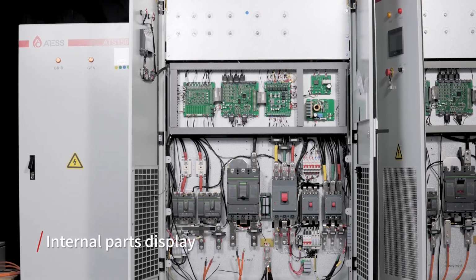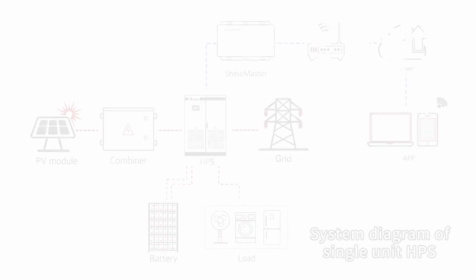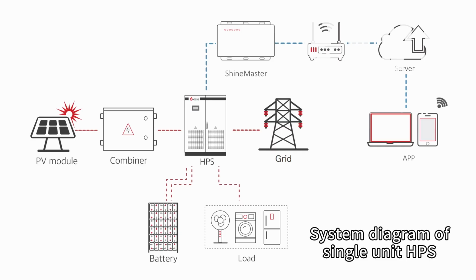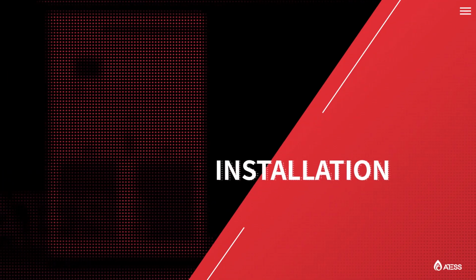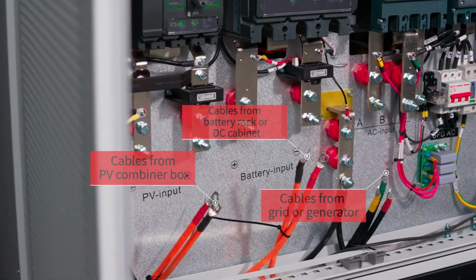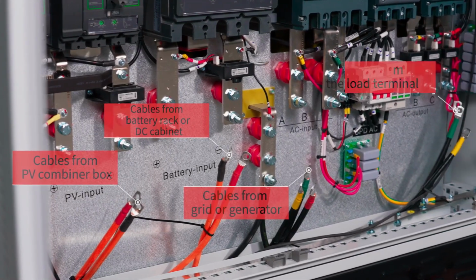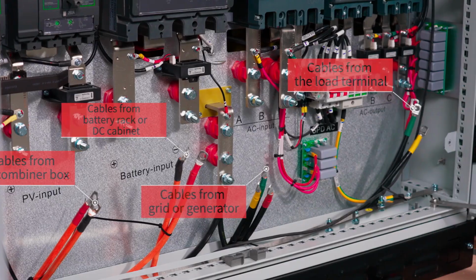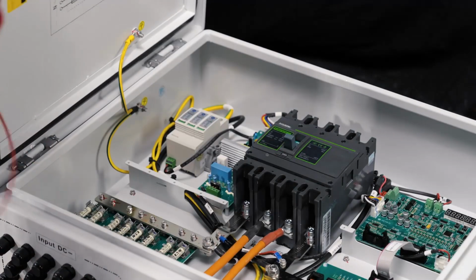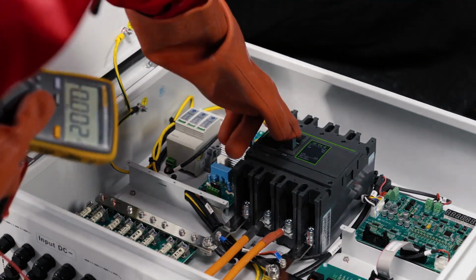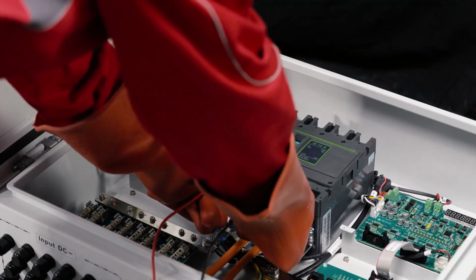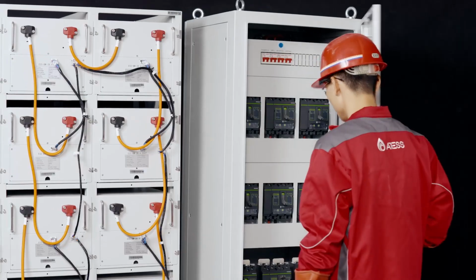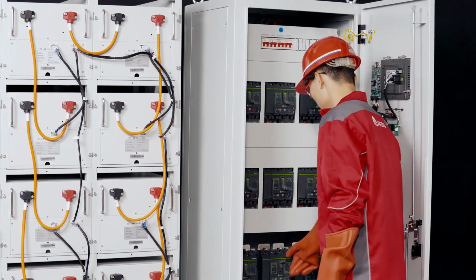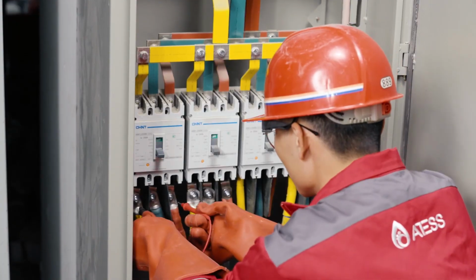Before we start wiring, firstly let's review the system diagram. Please thoroughly read the user manual before installation. Open the cable entry hole covers and pass all cables through. To ensure safety, turn off all the breakers and measure to ensure the whole system has zero potential. Disconnect power at the circuit breakers or disconnect switches to make sure all equipment is powered off.